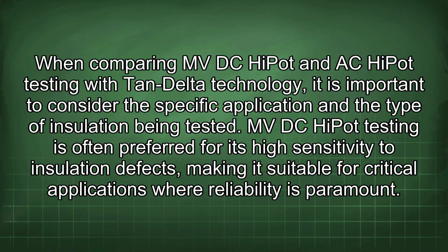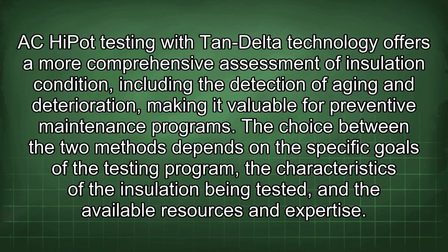MVDC HiPot testing is often preferred for its high sensitivity to insulation defects, making it suitable for critical applications where reliability is paramount. AC HiPot testing with tan delta technology offers a more comprehensive assessment of insulation condition, including the detection of aging and deterioration, making it valuable for preventive maintenance programs. The choice between the two methods depends on the specific goals of the testing program, the characteristics of the insulation being tested, and the available resources and expertise.